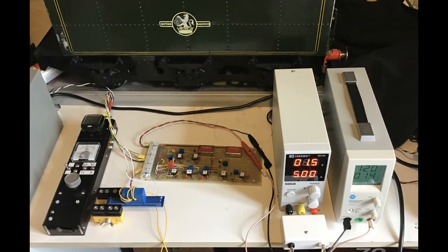We can see its operation here with a spare sensor. The maximum test circuit current that I have available is 5 amps. I've therefore fed this test circuit through the sensor 5 times, so the combination simulates 25 amps. When monitoring the tender current, the hand controller meter is scaled for 50 amps, full scale, so we can see it here showing half scale.